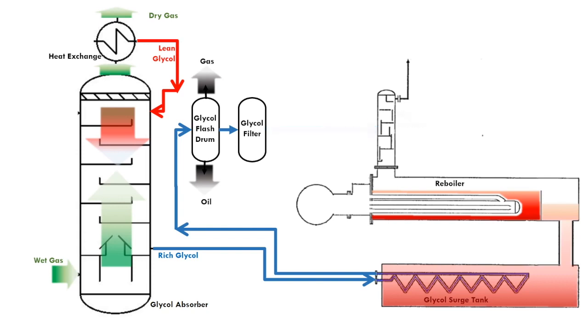The rich glycol then flows to the still column of the reboiler. The purpose is to remove the water. The glycol vapor condenses when it comes in contact with the cool glycol. Thus, condensed glycol will drop onto the tray in the still column and subsequently flows downwards.